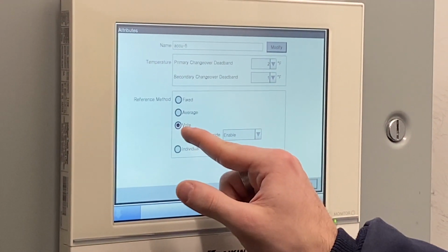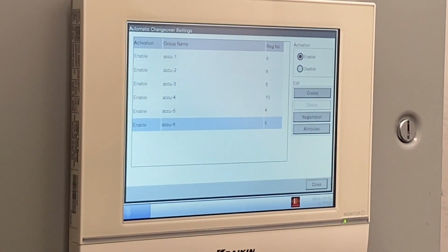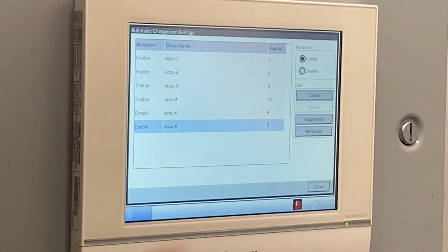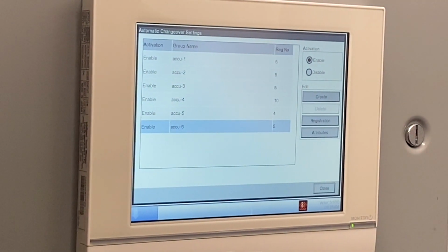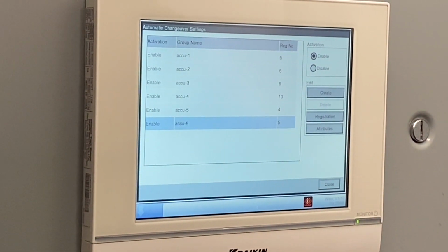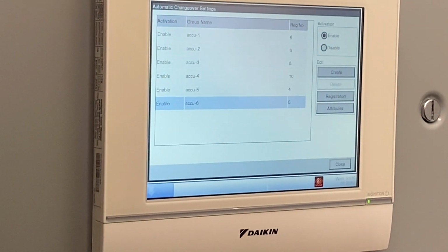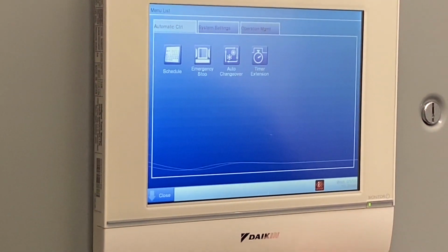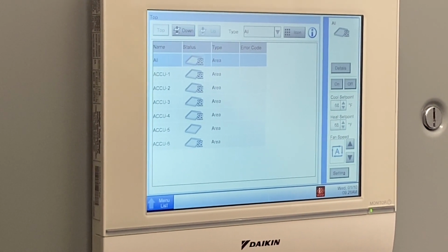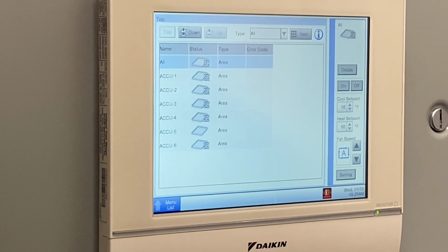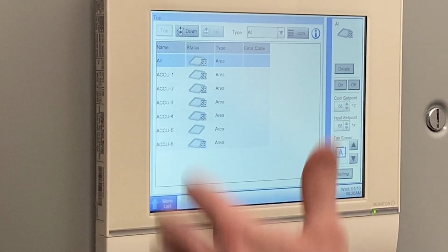It's going to be a vote. So what it means by vote, obviously, is majority minority rule. So if say you have 4 condensers that want heating and 2 condensers that want cooling, then obviously the four are going to win, because majority rules. So all of it's going to go into heating in that case. I'm pretty sure all these units here are heat pumps, not heat recovery, so it's all 2 pipe. So always keep that in mind, that it's going to be a majority minority rule.